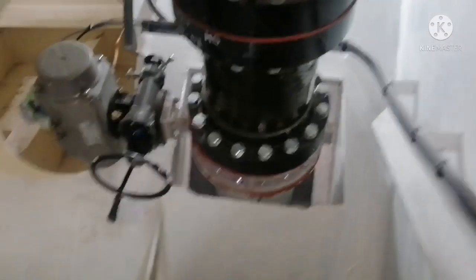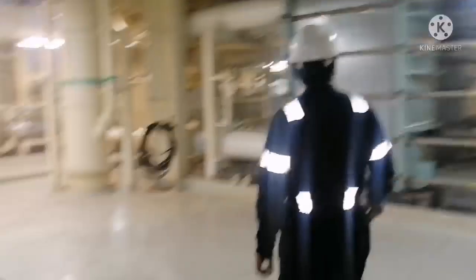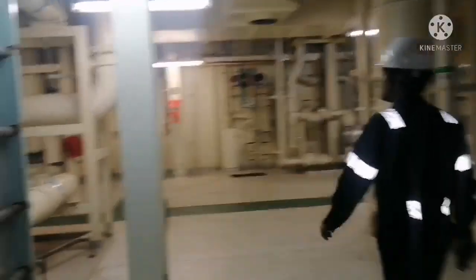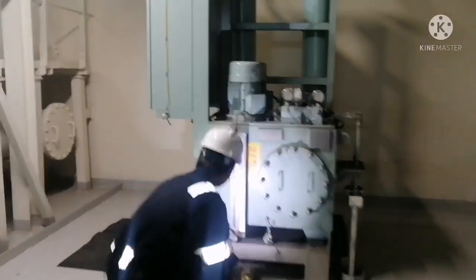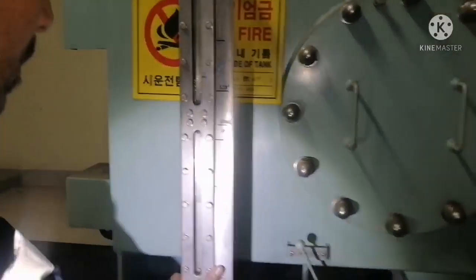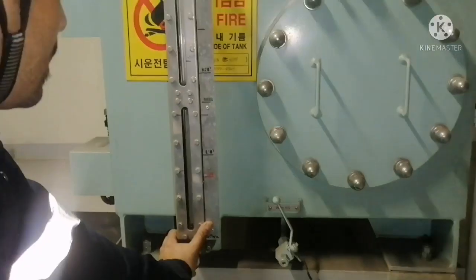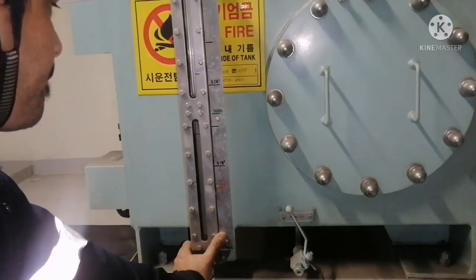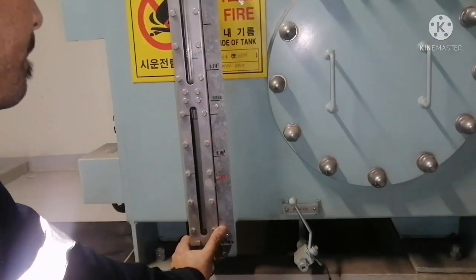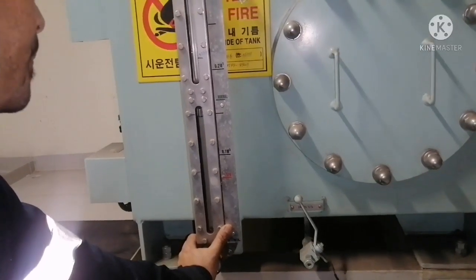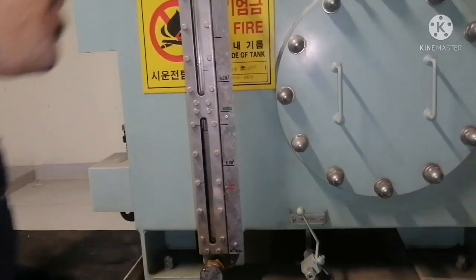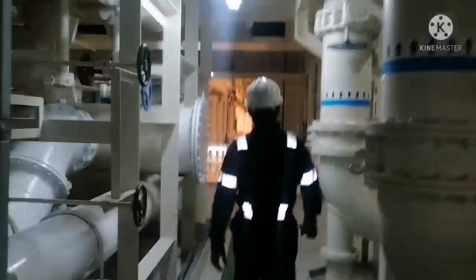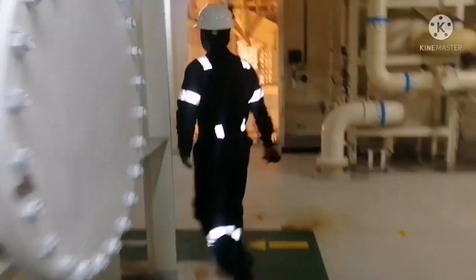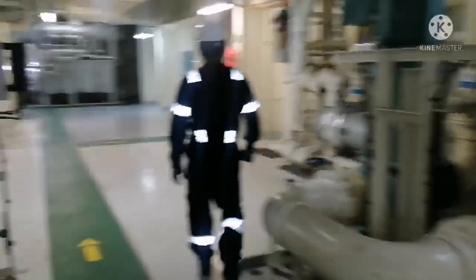So okay, I'm done with this LT cooler platform. Whenever you cross any platform, you ensure everything is okay. This is your remote quick closing valve tank. Just check the tank level. How do you need to check? Just press the button on the bottom side, so you can see the level start to rise and get stabilized somewhere. When it is stabilized, that is the exact level of your tanks. So I'm done with the LT cooler platform round.